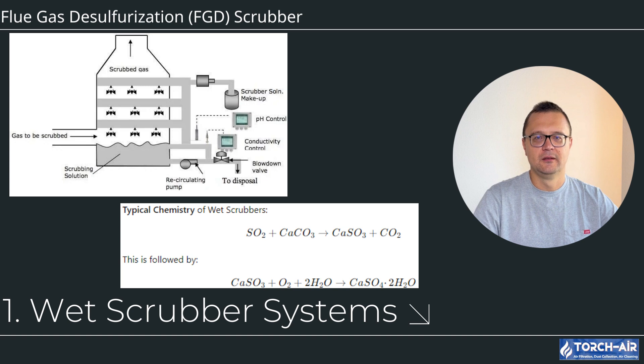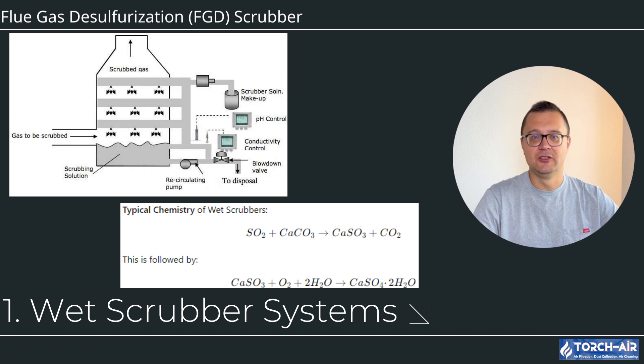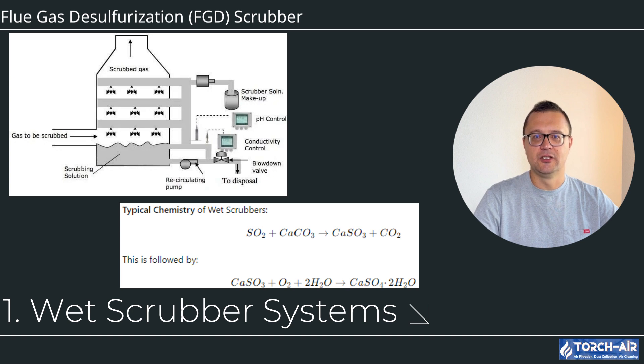Wet Scrubber Systems: The wet scrubber is the most common type of FGD system and uses a liquid, usually water mixed with an alkaline reagent such as limestone (CaCO3) or lime (CaO), to capture and neutralize SO2 in the gas stream. The flue gas containing SO2 enters the scrubber through the gas inlet. As the gas moves upward in the absorption section, it comes into contact with the scrubbing liquid sprayed from nozzles, initiating a chemical reaction that converts the sulfur dioxide into a liquid byproduct.